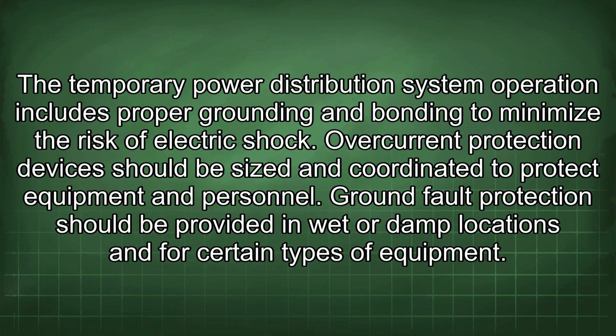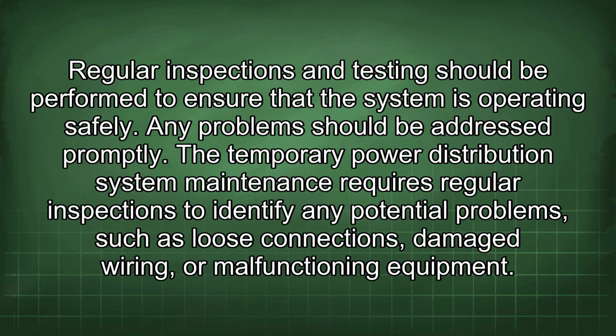Temporary power distribution system operation includes proper grounding and bonding to minimize the risk of electric shock. Overcurrent protection devices should be sized and coordinated to protect equipment and personnel. Ground fault protection should be provided in wet or damp locations and for certain types of equipment. Regular inspections and testing should be performed to ensure that the system is operating safely. Any problems should be addressed promptly.